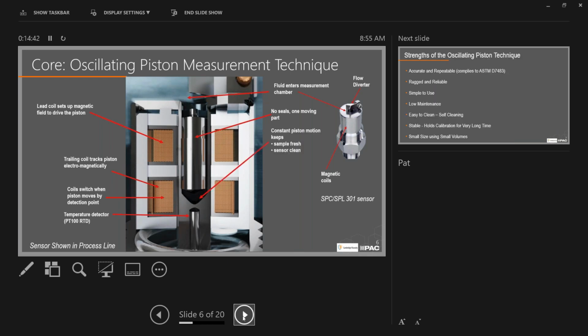So that piston action pumping up and down is helping to exchange the fluid, right? As it moves up, fluid is being drawn underneath it, and as it moves down, it displaces that fluid. That makes it self-cleaning because it's constantly scrubbing, okay? And we're not sensitive to vibrations, we're not sensitive to air bubbles and entrained air, we're not sensitive to particles. What happens with particles is if they're too large, they can't come in, and if they're too small, they help constitute part of the viscosity of that fluid, and they just move in and out of the sensor.